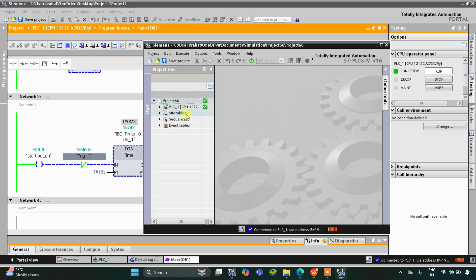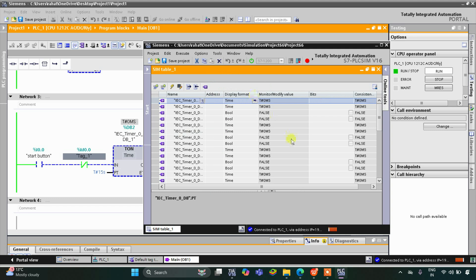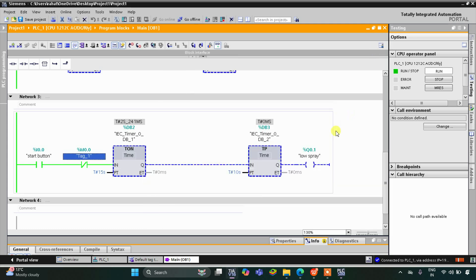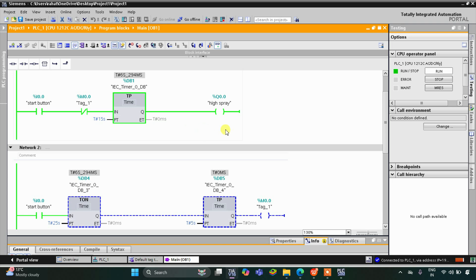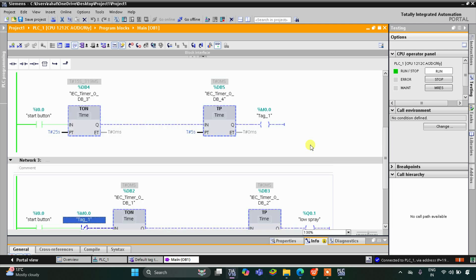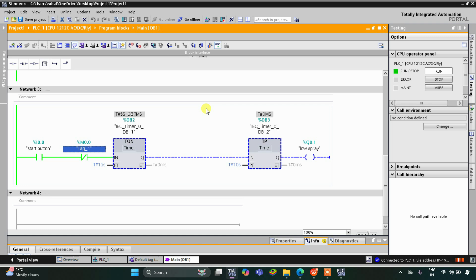I will go to Simulation Tables > Simulation Table 1, right-click and load project tags, then activate the start button. There will be a high spray for 15 seconds — you can see it counting: 7, 8, 9, 10, 11, 12, 13, 14, 15 — and high spray gets off. Then there will be a low spray for 10 seconds: 3, 4, 5, 6, 7, 8, 9, 10 — and low spray gets off. Then M0.0 gets true, and after M0.0 gets off, high spray gets on again, followed by low spray. That was all about this example, thank you for watching.